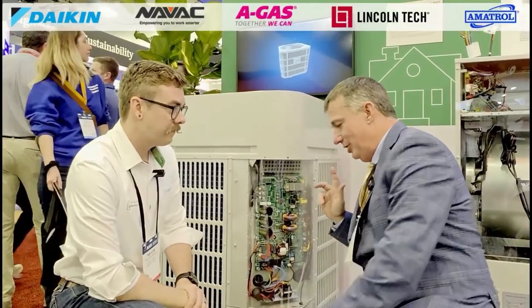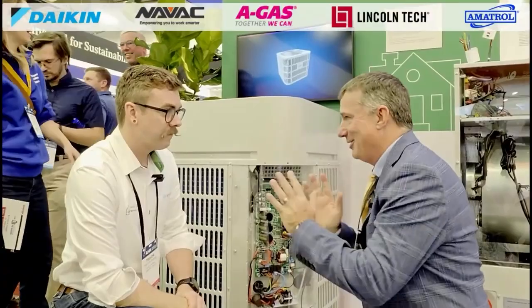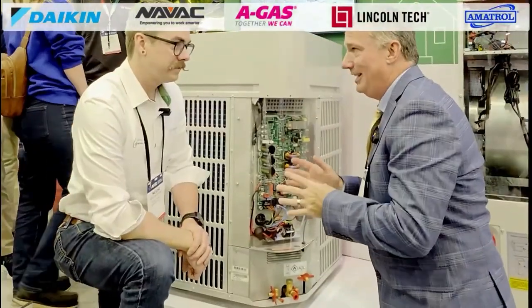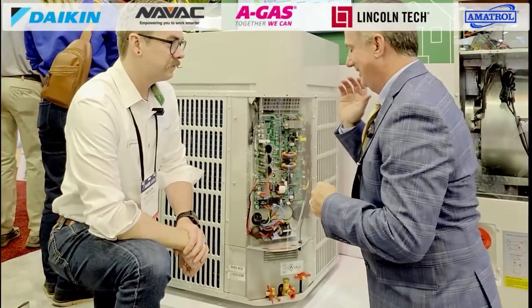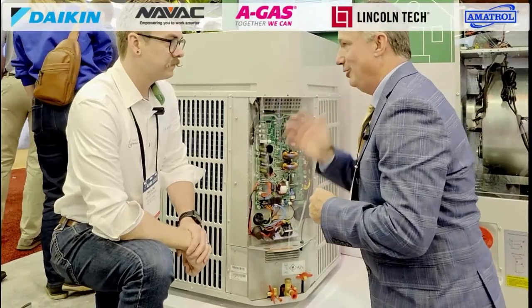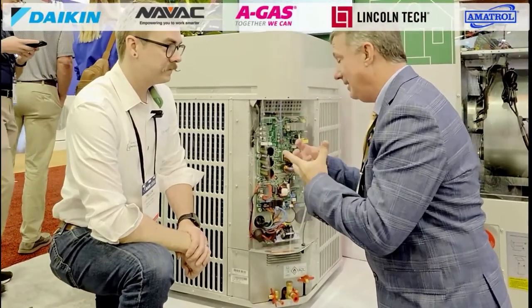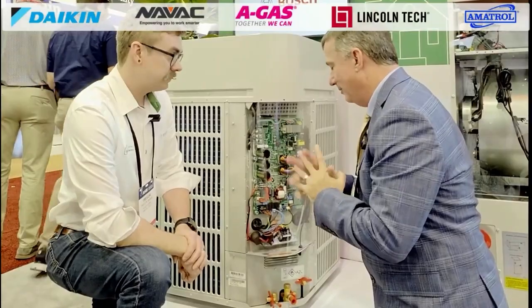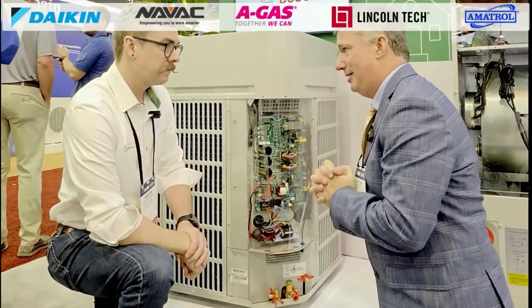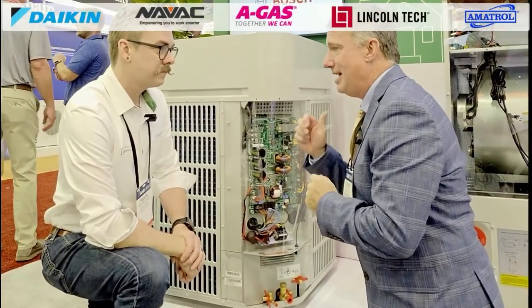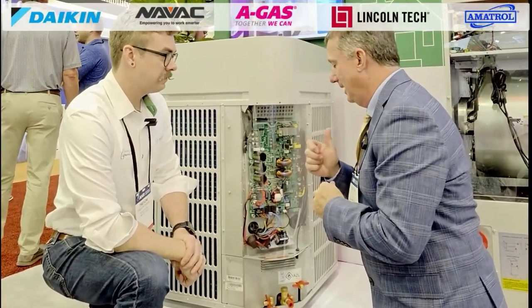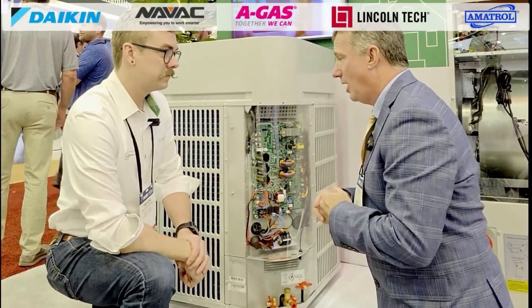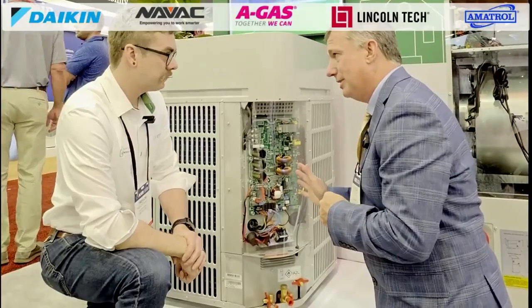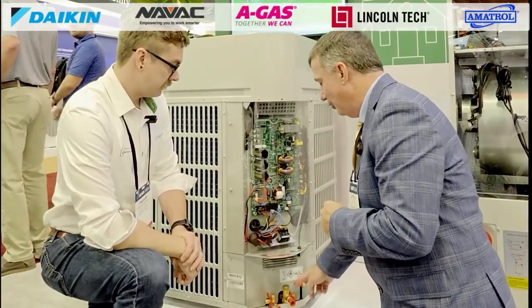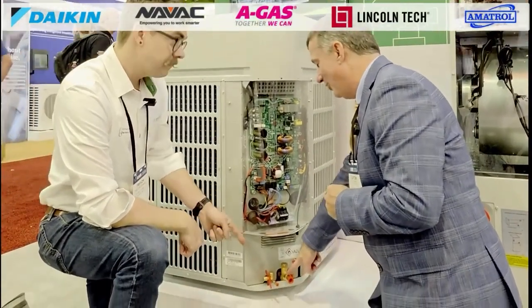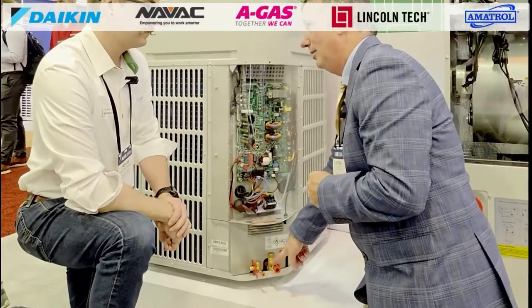There's a feature I can't wait to talk about. There's a big controversy in the industry: do we braze, do we flare, do we use compression style fittings or any type of mechanical fitting? Bosch has gone to the point of saying those mechanical fittings, if UL rated and done properly, are a really good option, especially with A2L mildly flammable refrigerants. You've actually gone to a pre-installed mechanical connection prepped for mechanical fittings.